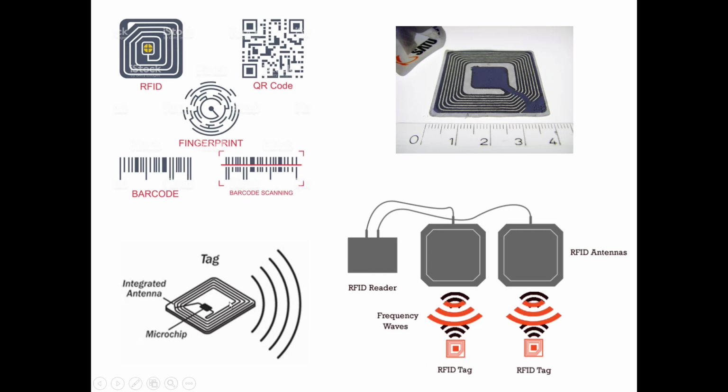I prefer the use of the RFID tag because, as we said, we have two types, the passive and active. The active is preferable because it helps us, especially in the case of having a large number of medical devices in our inventory.